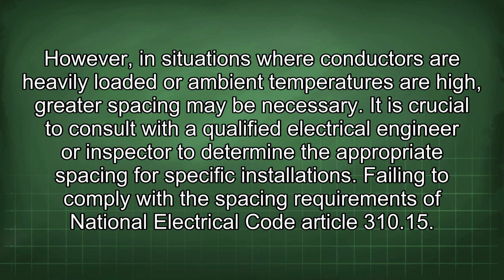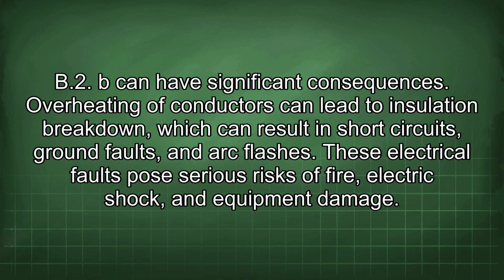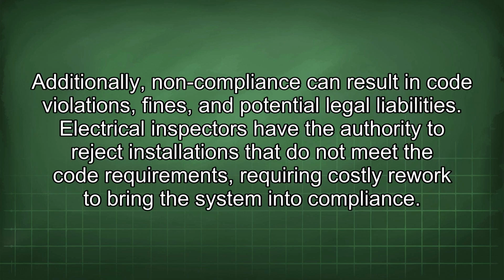Failing to comply with the spacing requirements of National Electrical Code Article 310.15.B.2.b can have significant consequences. Overheating of conductors can lead to insulation breakdown, which can result in short circuits, ground faults, and arc flashes. These electrical faults pose serious risks of fire, electric shock, and equipment damage. Additionally, non-compliance can result in code violations, fines, and potential legal liabilities.